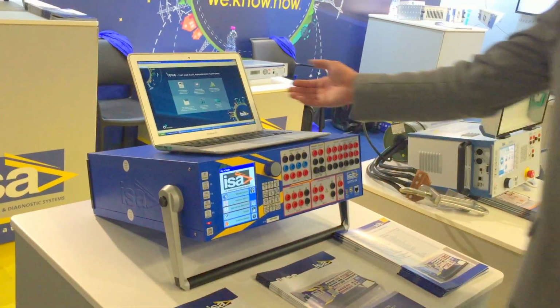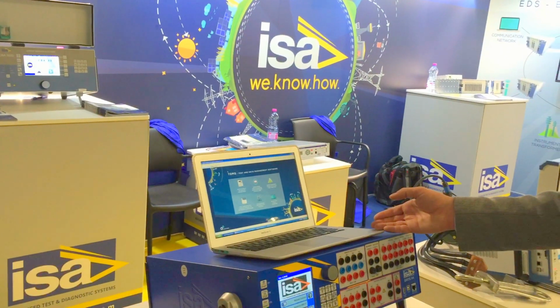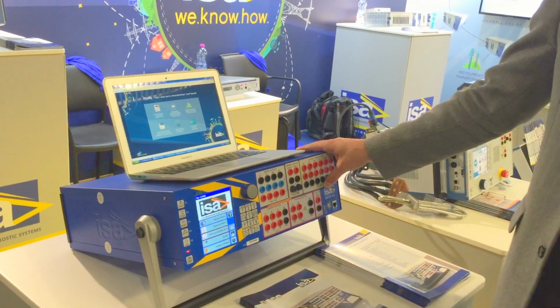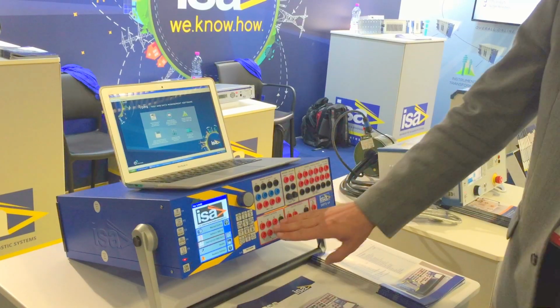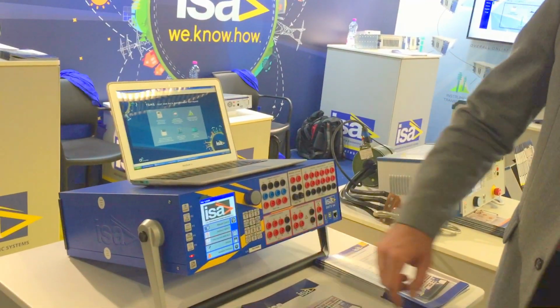Hi, we're at CIGRE and we're going to present a few devices for you. So of course, this is our DRTS64 with TDMS, our secondary injection relay test set. We have 4 versions. This is one of the most popular ones, DRTS64 with 6 currents and 4 voltages, 32 amps per channel, 300 volts output, and the ability to connect in parallel or series.